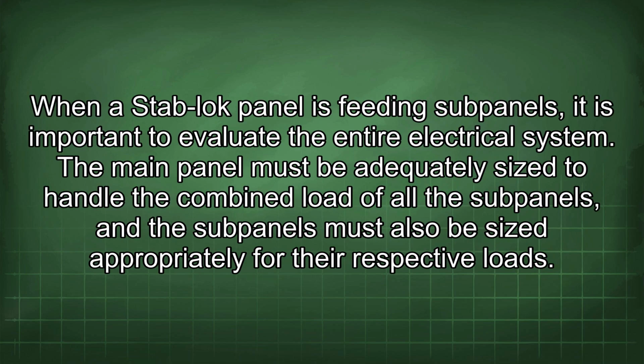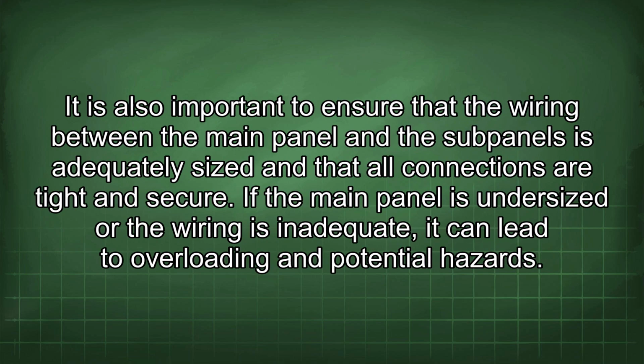When a Stab-lok panel is feeding subpanels, it is important to evaluate the entire electrical system. The main panel must be adequately sized to handle the combined load of all the subpanels, and the subpanels must also be sized appropriately for their respective loads. It is also important to ensure that the wiring between the main panel and the subpanels is adequately sized and that all connections are tight and secure. If the main panel is undersized or the wiring is inadequate, it can lead to overloading and potential hazards.